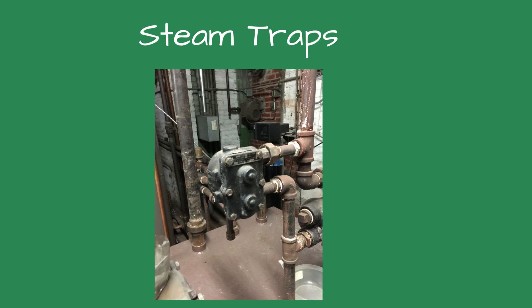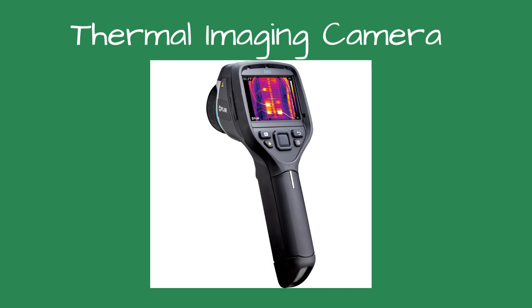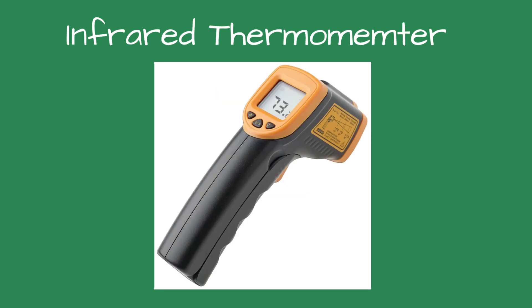In this case, it was less than 10 degrees. Using my thermal imaging camera, I checked the piping downstream of the steam traps in the room. The thermal scan showed elevated temperatures coming from the discharge pipe of the two steam traps. An infrared thermometer may be used as well. The infrared contactless thermometers work well on black iron pipes, but not as well on copper tubes.